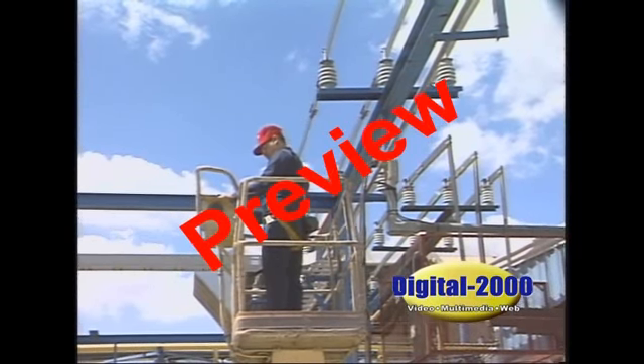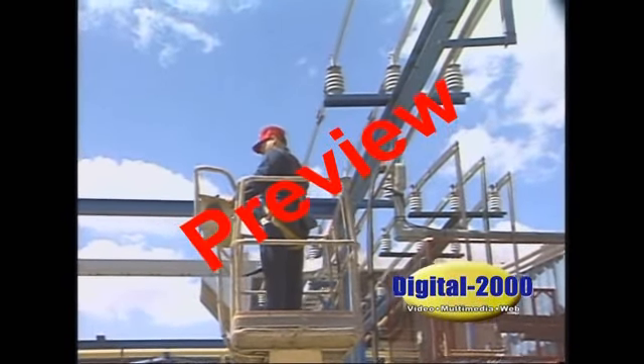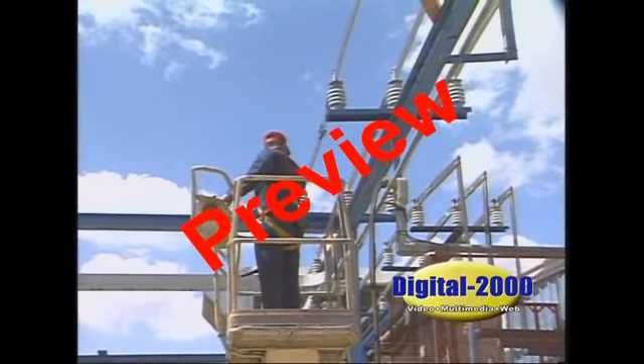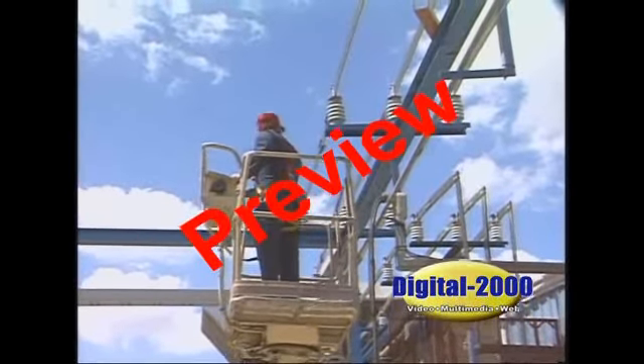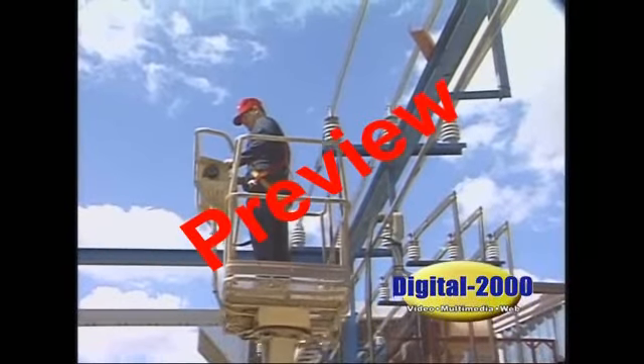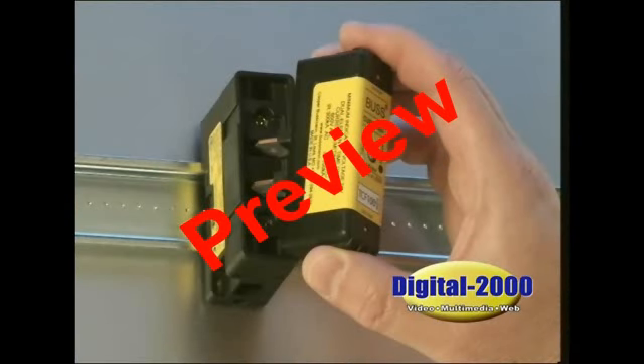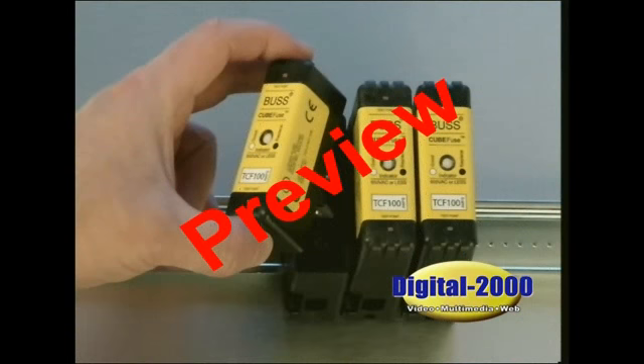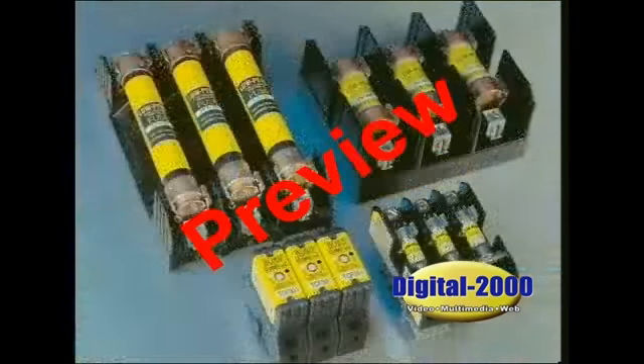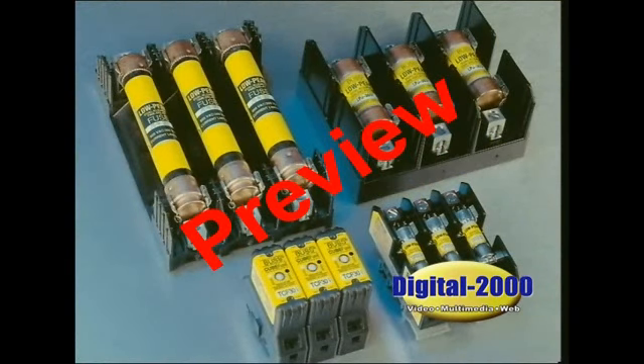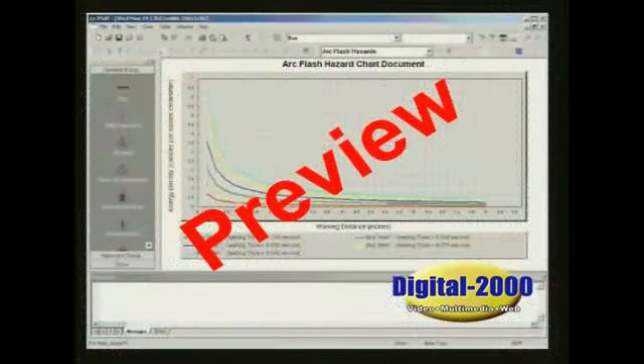The safety activity in the electrical industry these days is focused on shock and arc flash hazards. Everyone knows about electrical shock, but we're still experiencing deaths and serious injuries each year from shock hazards. One of the best ways to prevent shock is to utilize finger-safe products and non-conductive covers or barriers. If all the electrical components are finger-safe or covered, a worker has a much lower chance of coming in contact with a live conductor. There are new fuses that are classified as finger-safe as well. The new requirement for NFPA 70E to reduce the risk of injury due to shock and arc flash hazards is for a flash hazard analysis.